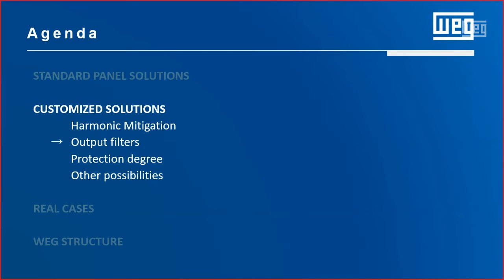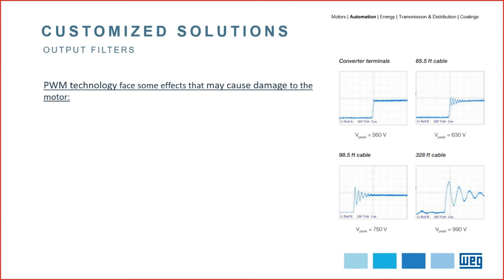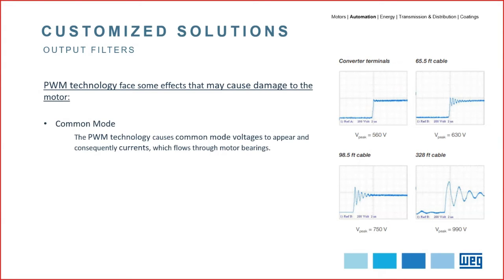Another customization option is the inclusion of an output filter inside the VSD panel. As known, all motors fed by a variable speed drive with PWM technology face some effects that may cause damage to the motor. The PWM technology causes common mode voltage to appear and consequently currents, which flow through the motor bearings, and it can also affect the VSD control and cause unexpected ground faults.